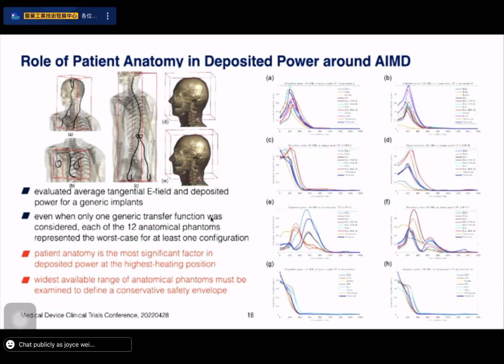But what we've shown in this work is that using these 12 anatomical models and only a single generic device, we can show that each patient can be the worst case for at least one configuration. So here you see the deposited power for 12 anatomical models. And for each anatomical model, there's a point where it's the worst case, including the skinny boy, including the Korean lady, including the fat guy, including everybody. So everybody's the worst case for at least one scan in at least one position. And this is without considering different devices. It's all with one device, 2 polarizations, and this is at 128 megahertz in this example.